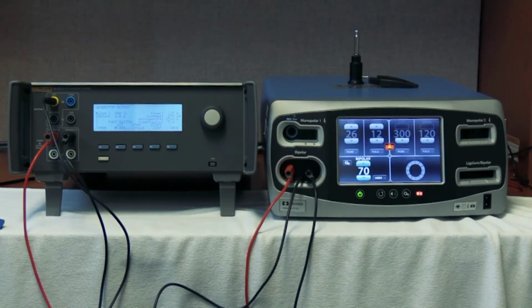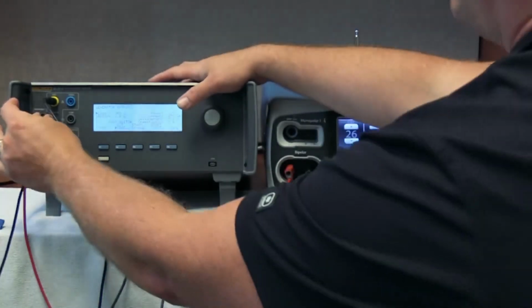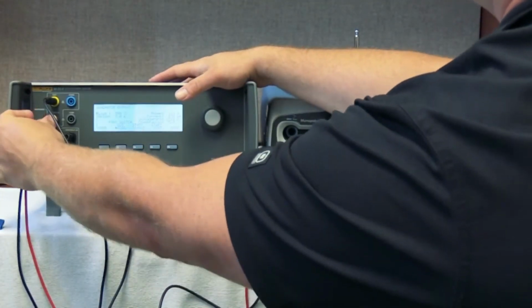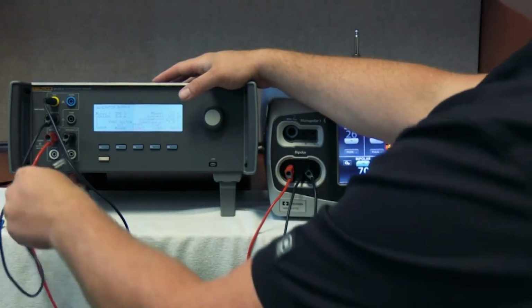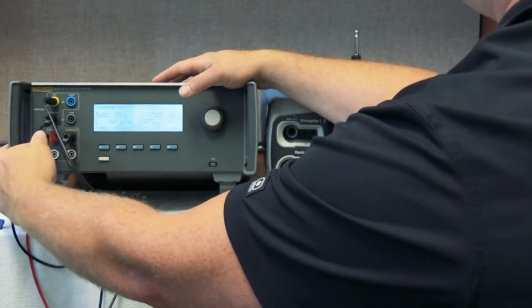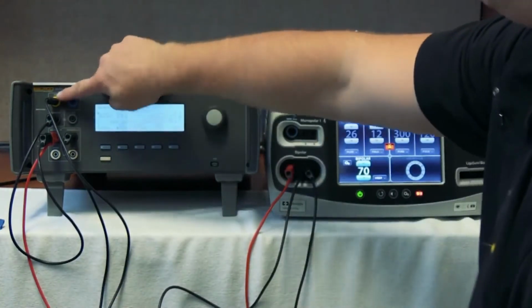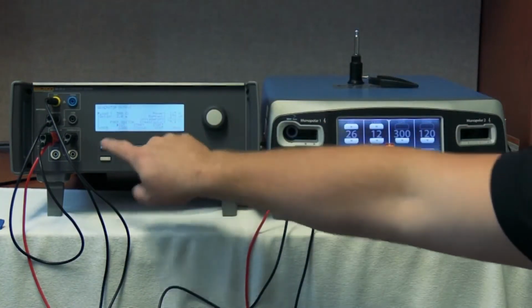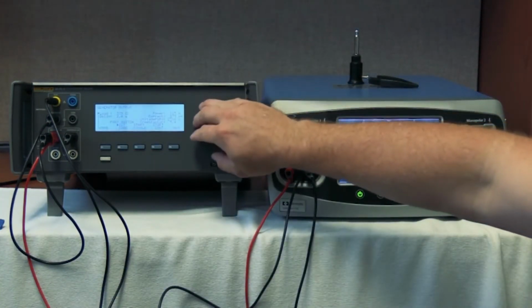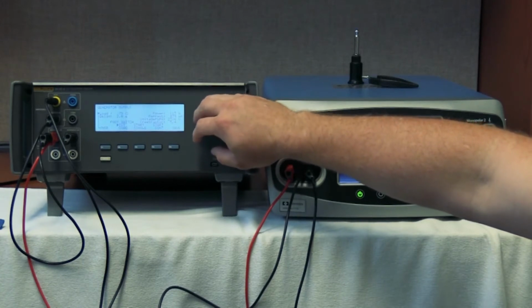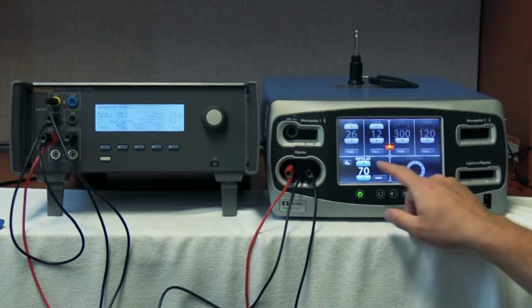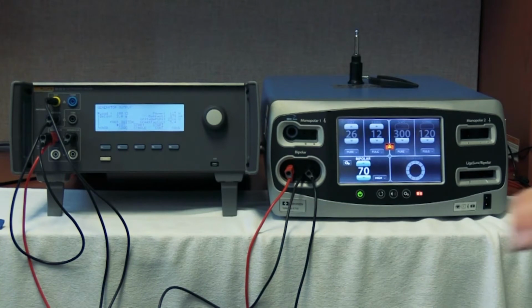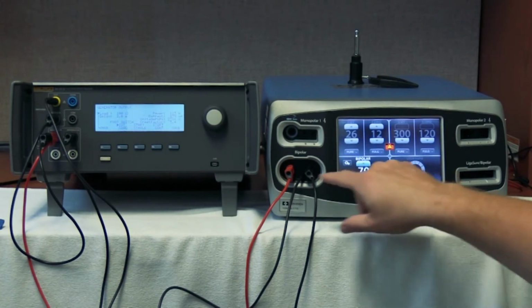Now we need a common jumper here, so we're going to run this common jumper from the slit section to the back of the red port again, just like we did for monopolar. Since we're plugged into cut, we're going to select cut with the foot switch. We're going to take this down to 100 ohms - again, refer to your service manual to find out where you want that. Here we have 70 watts.